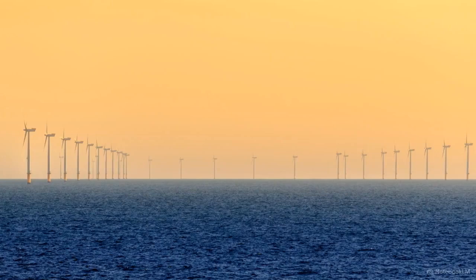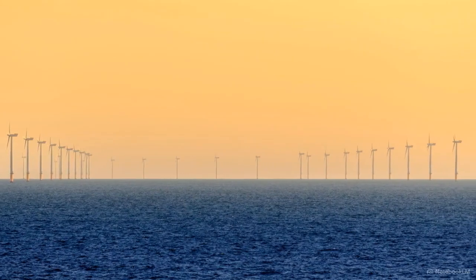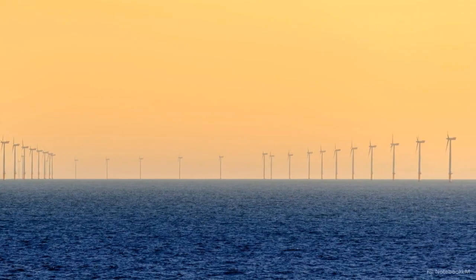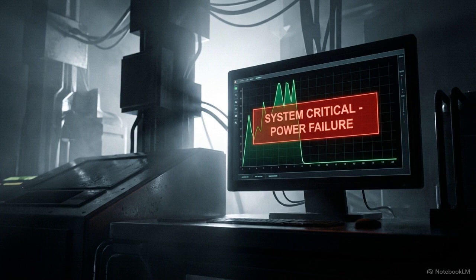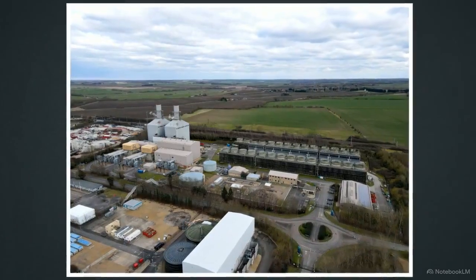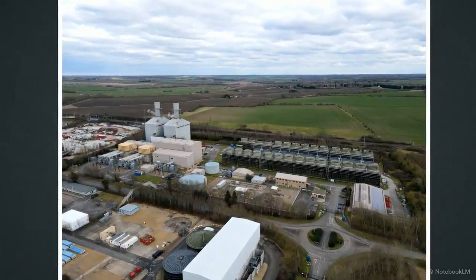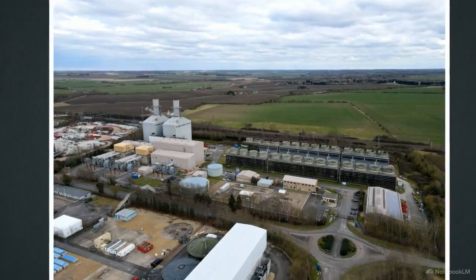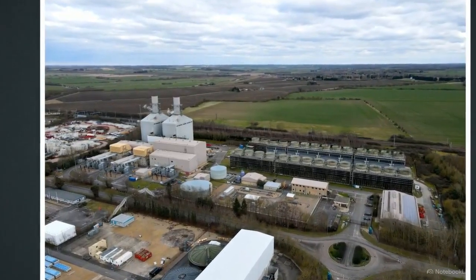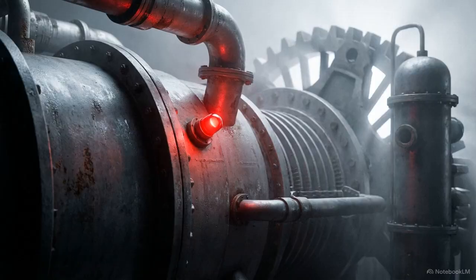At the Hornsea One offshore wind farm, overprotective software detected the voltage dip. Interpreting the fluctuation as a critical error, the control system rapidly slashed the farm's power output. Nearly simultaneously, at the Little Barford gas plant, the same electrical disturbance caused a discrepancy between two turbine speed sensors. The plant's automated safety logic triggered an immediate shutdown to protect the machinery.